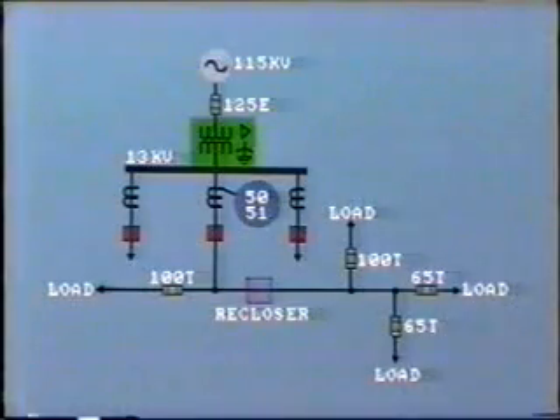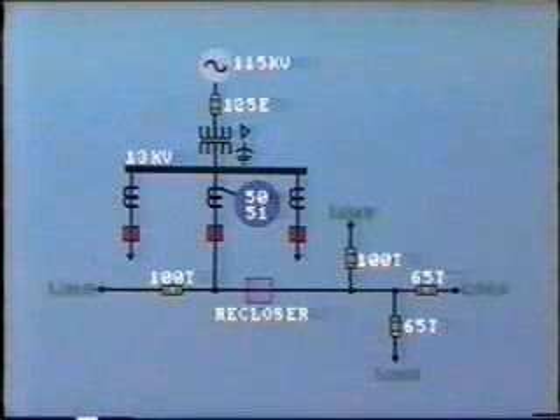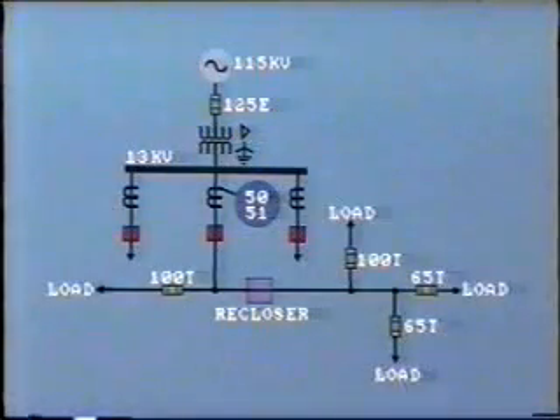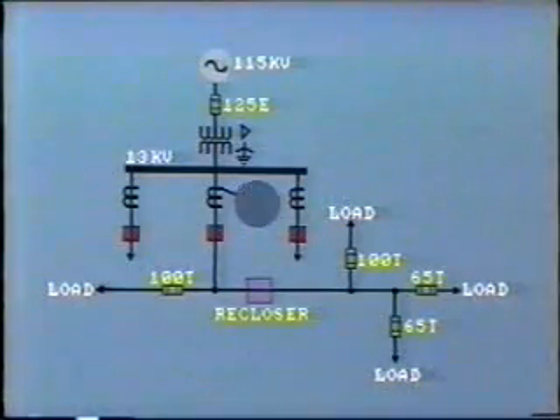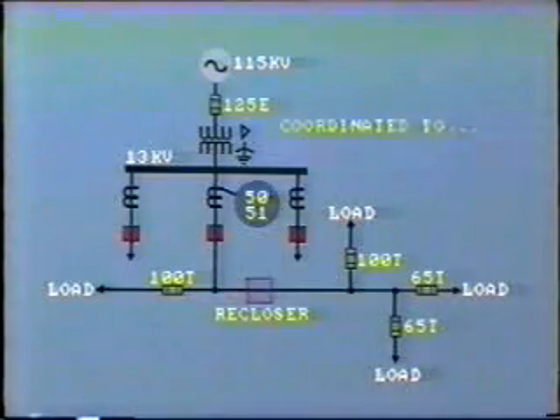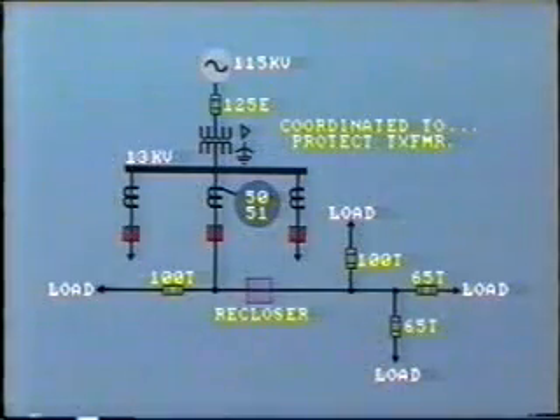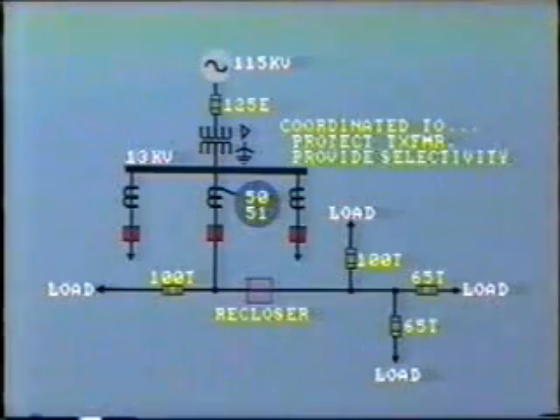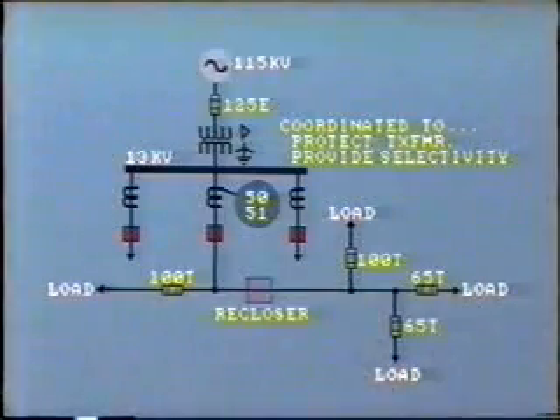This transformer is feeding a radial distribution feeder, which itself supplies several load centers. All of these protective devices, the fuses, the reclosers, and the breaker overcurrent protection, need to be coordinated. First, to protect the transformer from damage due to overload, and secondly, to provide selectivity in isolating the faulty circuit only.